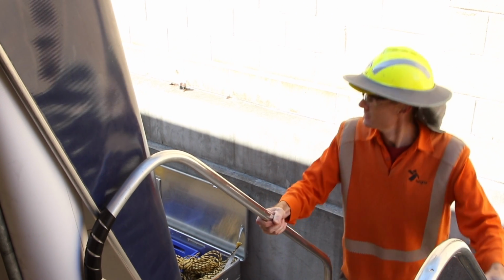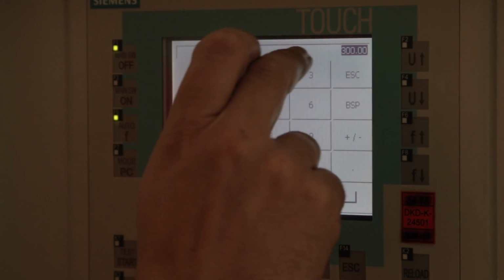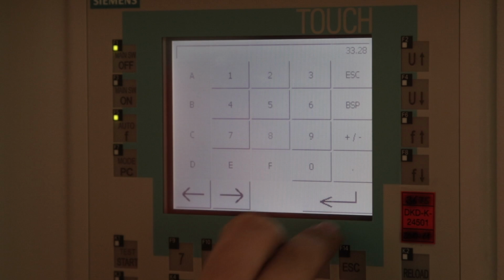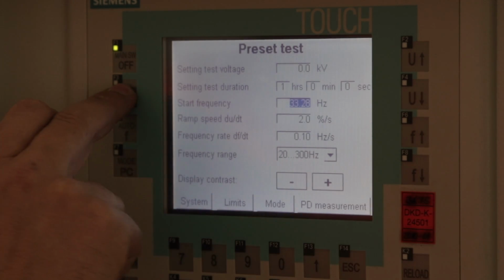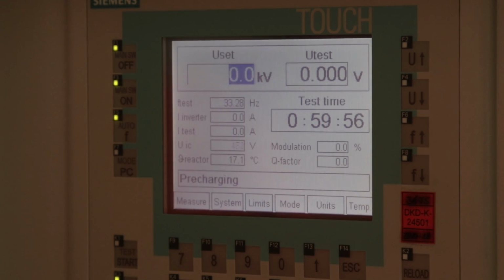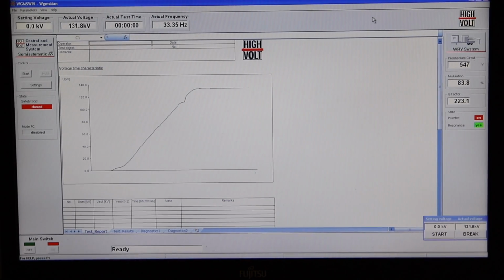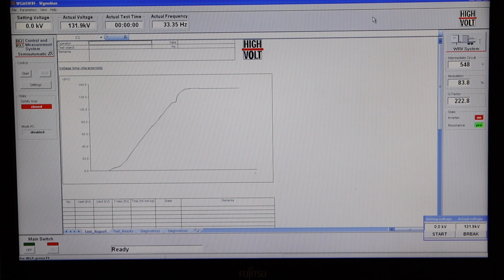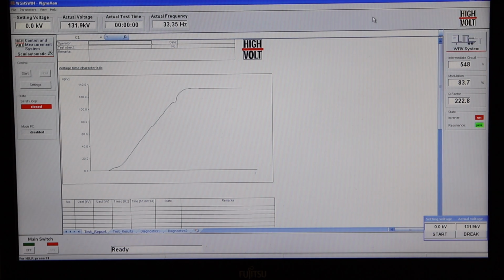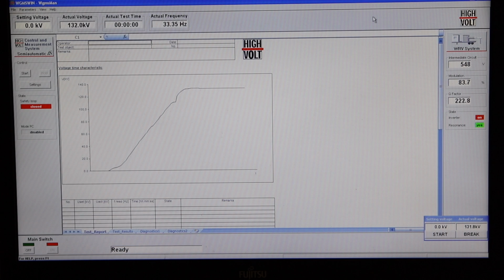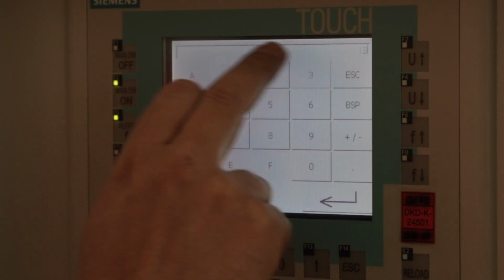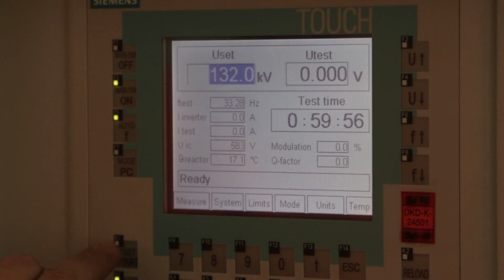Coming on! All clear! The next step is to find resonance to enable testing of large feeders at high voltage. Finding resonance is achieved through the use of the control panel interface and the software on the laptop, wirelessly connected with the test trailer. A preliminary check is performed at 5 kV before the voltage is ramped up to the required test voltage. The test voltages required for commissioning are defined in the Ausgrid network standard NS161. For the test today, 132 kV will be applied and the test duration is 1 hour.